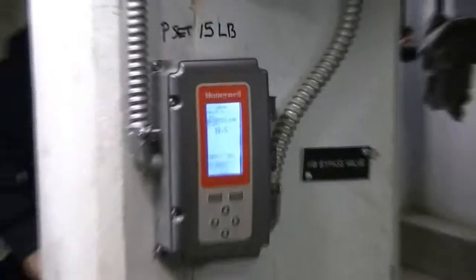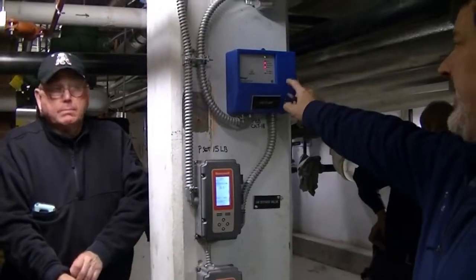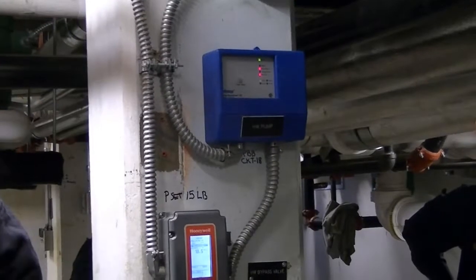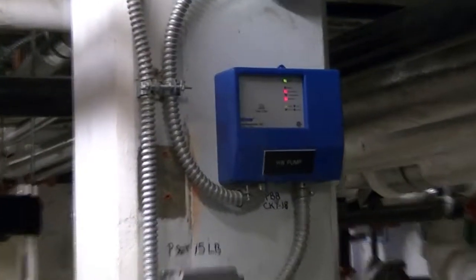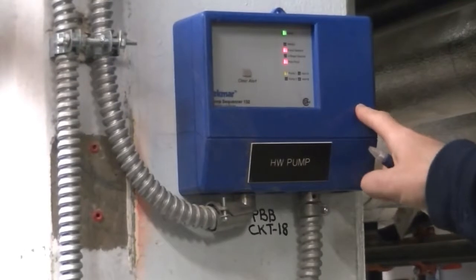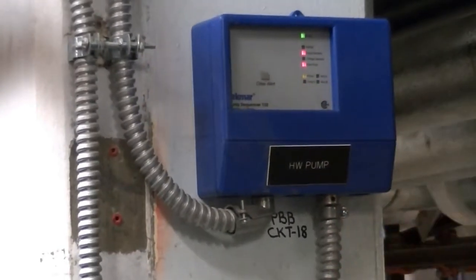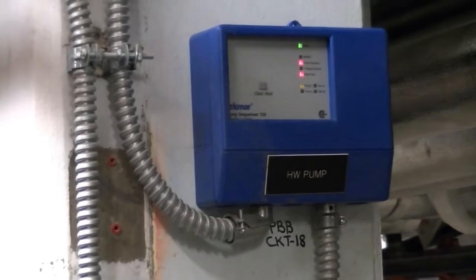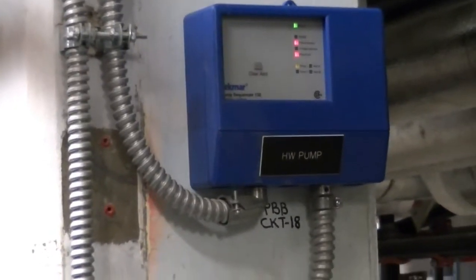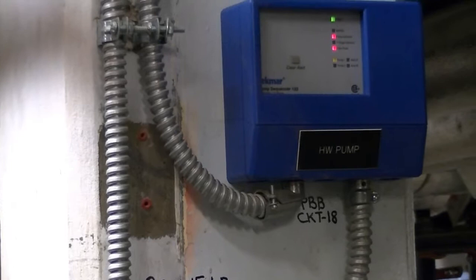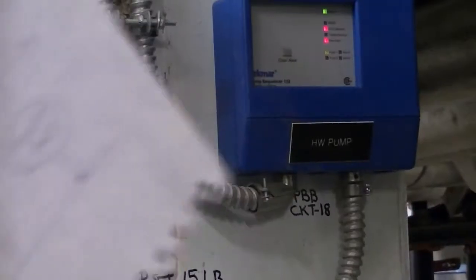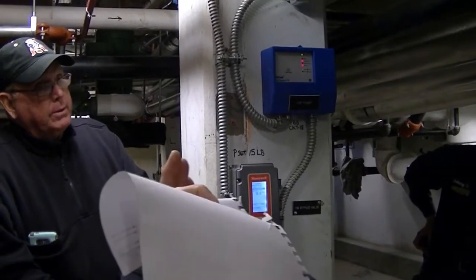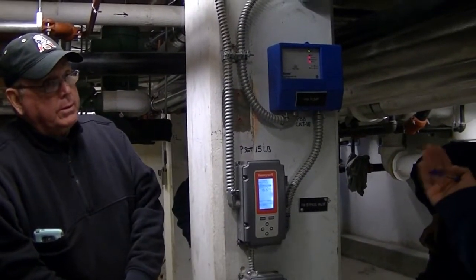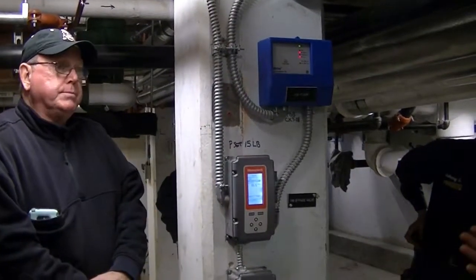Okay, what do the pump sequencers do? First, the heat and hot water pump gets enabled and disabled based on the boiler controllers. When the boiler calls, it says I want the pumps to run, so this one will actually start one of the drives. Everyone know what lead-lag is? Lead-lag pumps? Usually it will select which one is the lead to run. Then after every week, I think we programmed it for every 7 days, it's going to swap the other one to be the lead. So you get equal run times, equal wear times, okay?